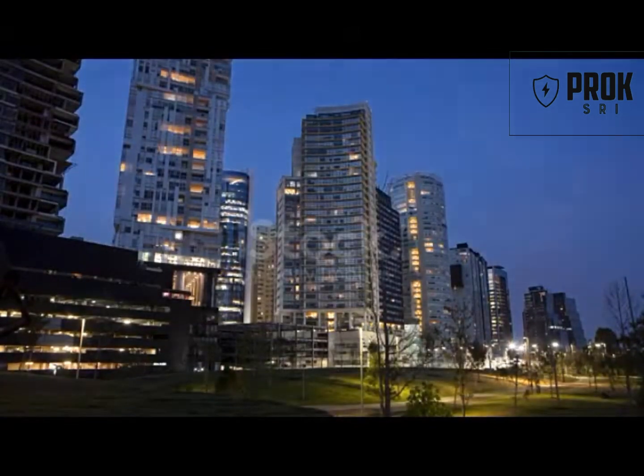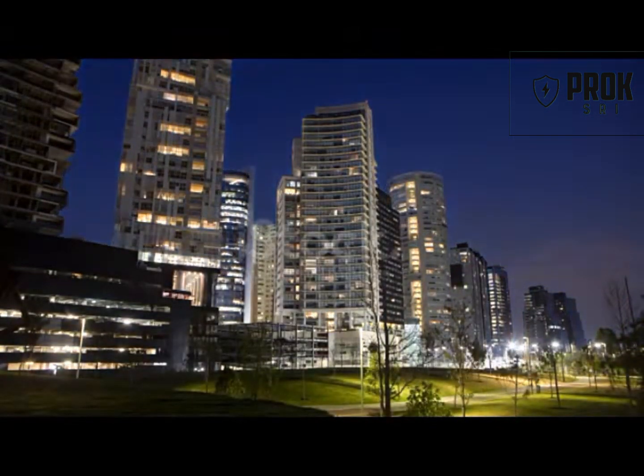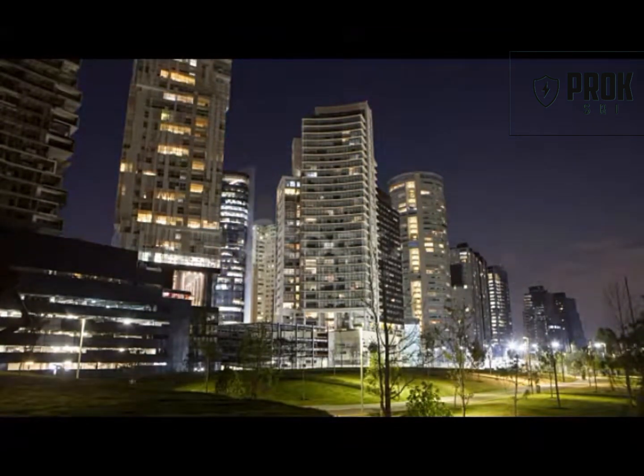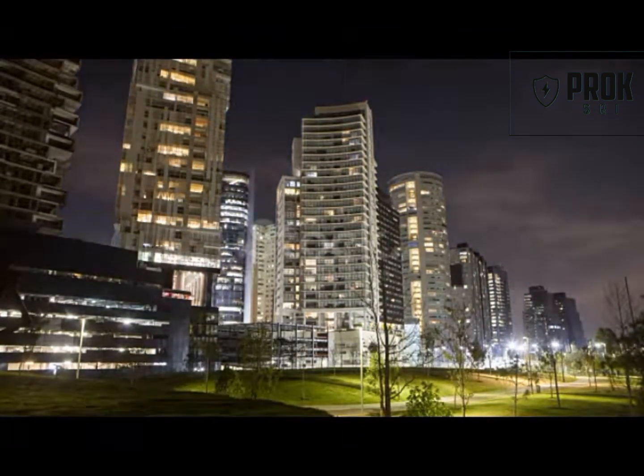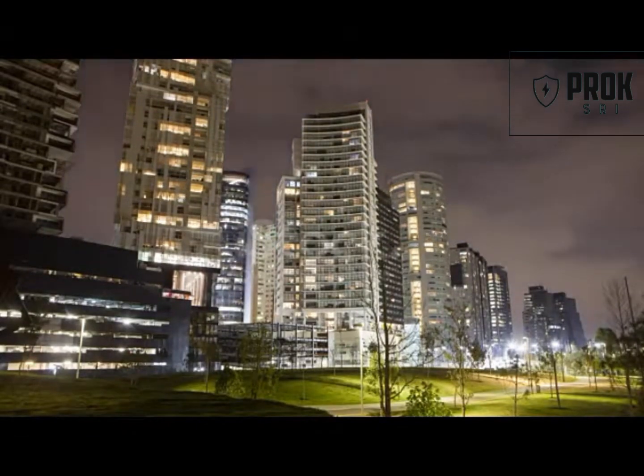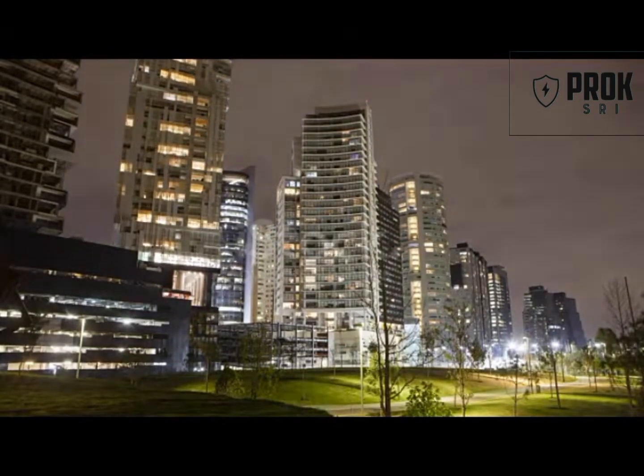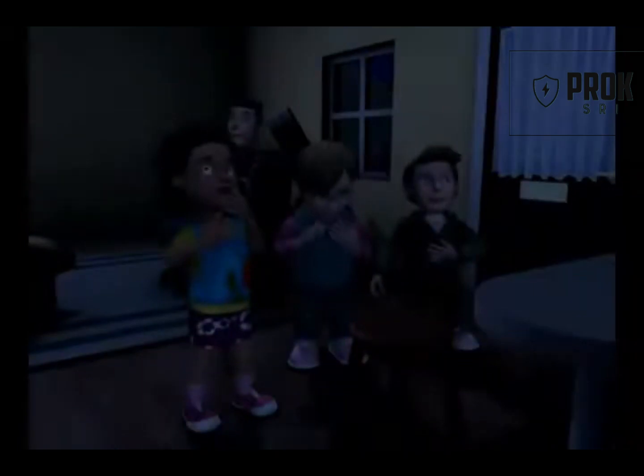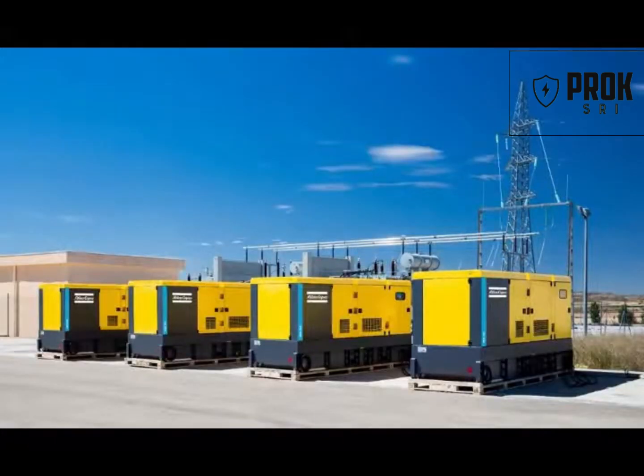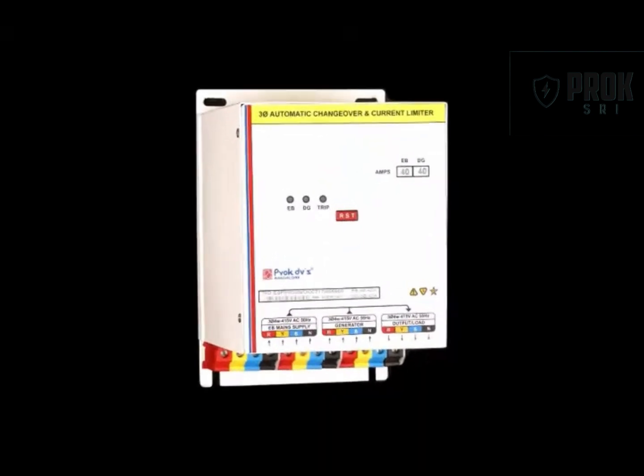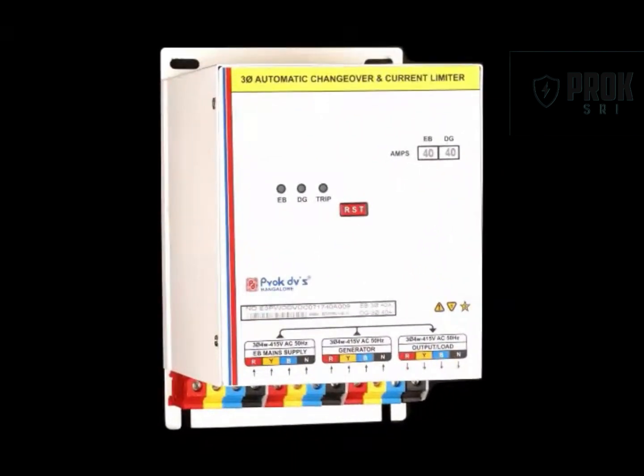Today we are at an apartment complex where our Prok DVS auto source changeover current limiters have been installed. ACCLs are basically used in apartment buildings where there is a power failure and diesel generators provide backup power. What makes ACCLs better than an auto transfer switch is that it not only has an electrical and mechanical interlock but also has a current limiter with under voltage and over voltage protection, which protects the diesel generator from overload in the event of a power failure.